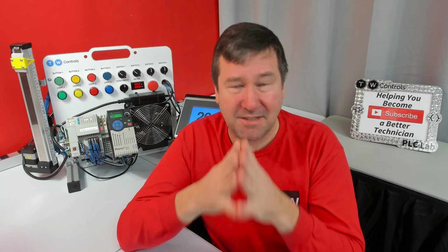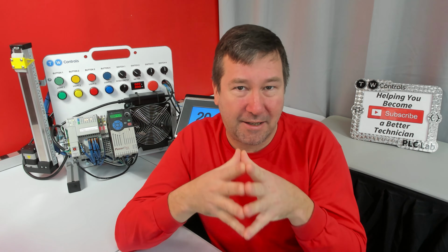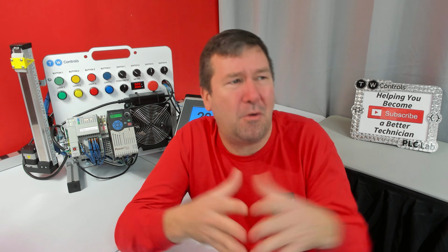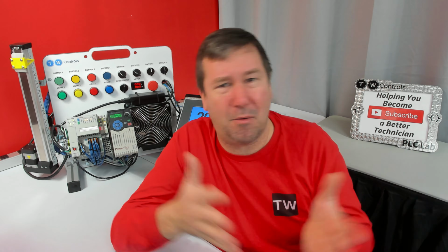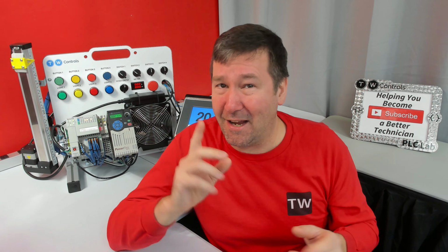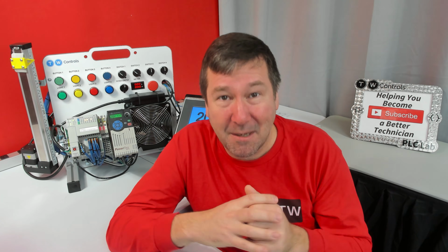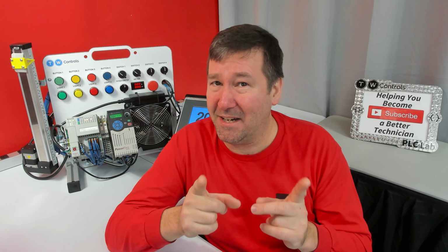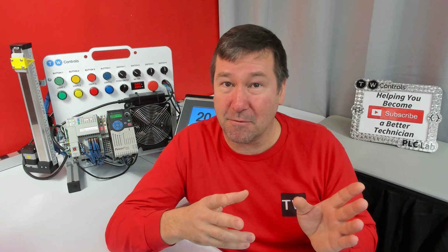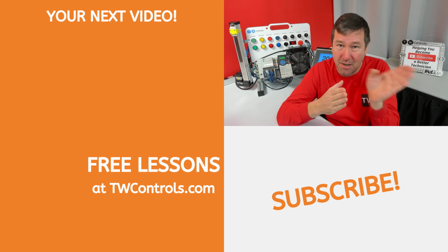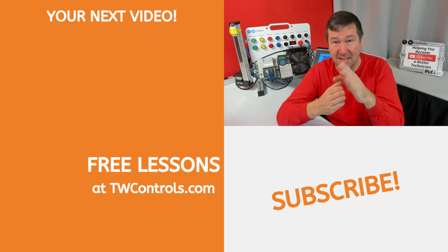Now, how do I wrap this back around to analog? Because that's where we started here. Those bits represent a certain amount of precision in your analog input. And that's what a lot of you are telling me: well, I didn't need that much precision, so why do I need to scale it that way? Well, you paid for it. And I've been in applications where the precision did matter. I'm going to start revisiting my PID series again, and we're going to find out a lot of your PIDs are not working well for this very reason, because you have made your analog signal too coarse and they're jumping too much from one point to the next point.